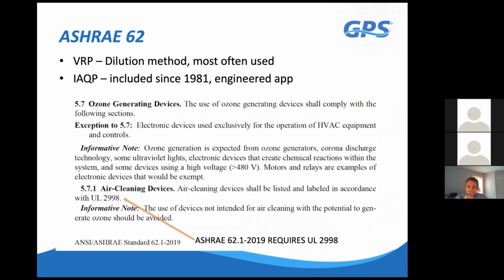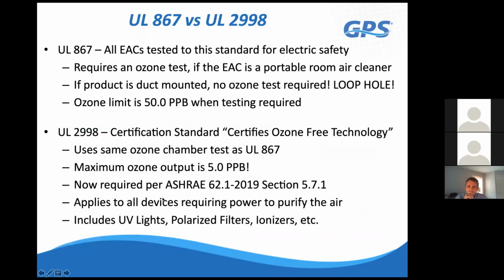The one thing I do want to point out here is that as of 2019, ASHRAE 62.1-2019 requires UL 2998 certification for air cleaning devices. So it doesn't matter if it's UV lights, electrostatic filters, or ionization systems like what we manufacture. If you have voltages in your system that exceed 480 volts, you're now supposed to be certified to UL 2998 to be compliant with ASHRAE, which means you don't generate ozone as a byproduct.